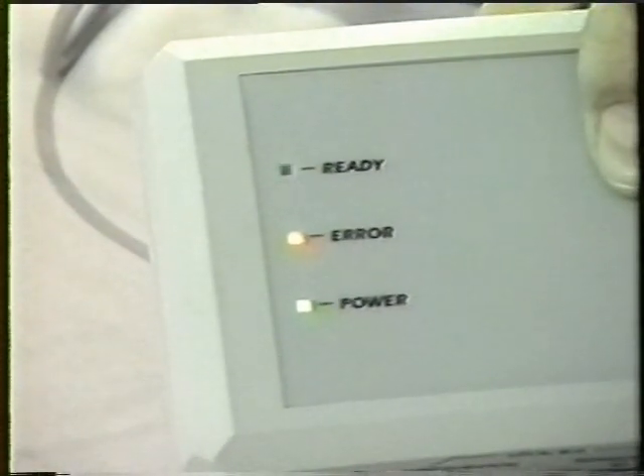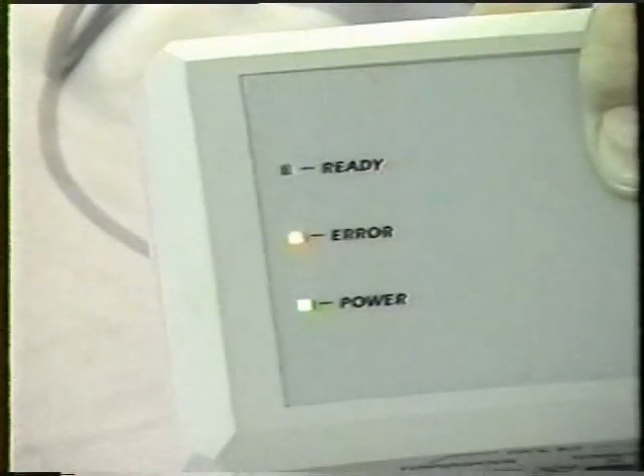This is an error on the U interface. Now we see it once per second — what's happening is it's syncing up on the ST. And now it's completely synced up. When we disconnect the U interface, we have a problem on the U. The reason it's coming back up is that I've plugged it back in and it's synced, and now it's syncing up again with the user equipment.